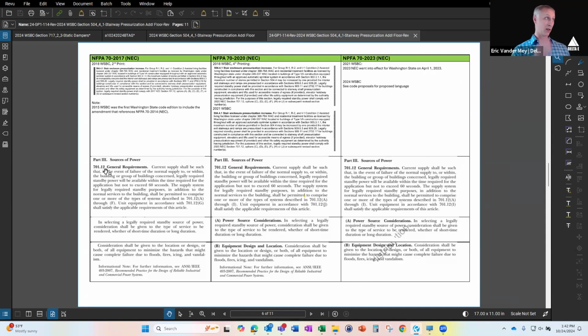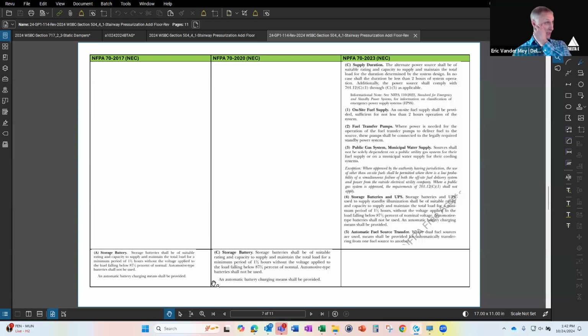Section 701.12, sources of standby power for legally required standby power. There's been quite a few section changes to this section in the NEC, in NFPA 70, over the last few years. As you can see, the first section used to be one section, and now they've broken this up into A, B. So some of these general requirements for the legally required standby power source are now specific subsections. So we definitely do need to update the section lettering in the 2024 code and also in our 2021 code that's currently in effect.